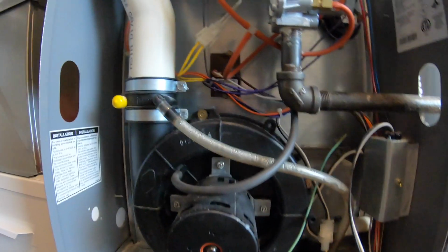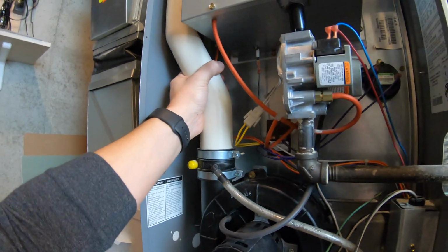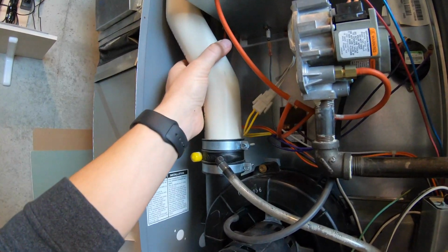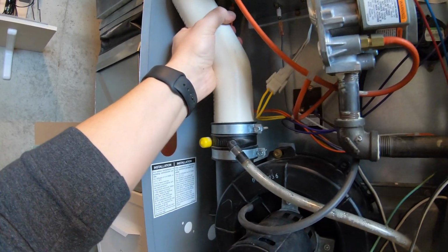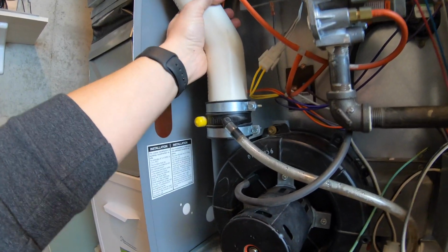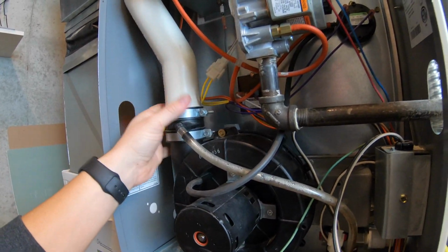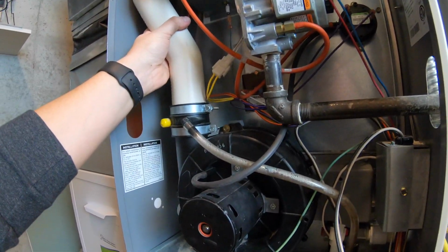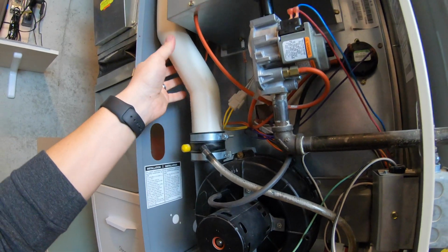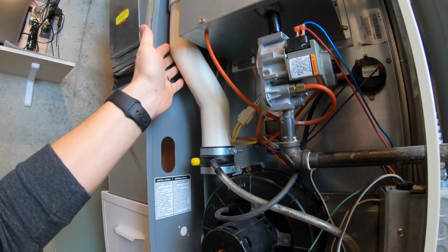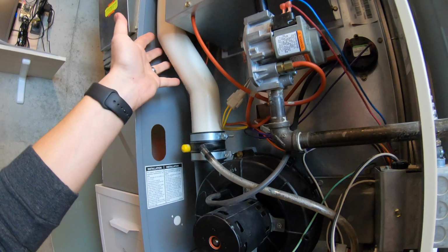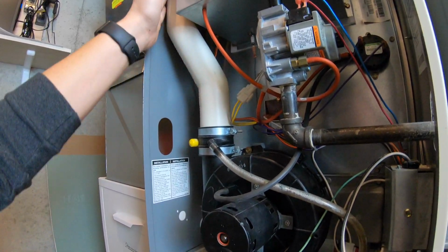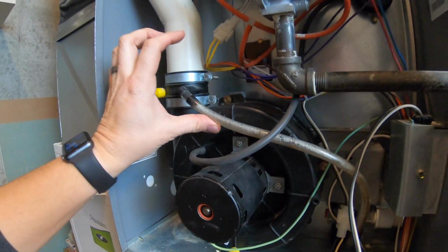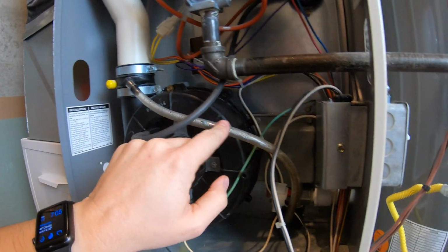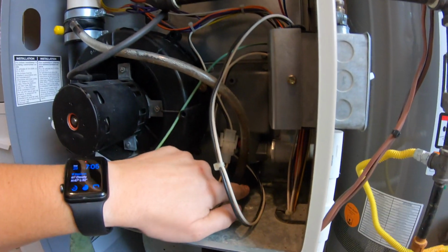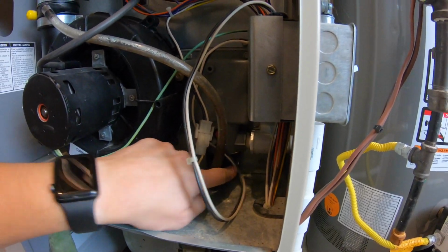Then this furnace is a condensing furnace. So the air going out through this pipe is very cool compared to your 80% furnaces or the older style furnaces that burned a lot hotter. The exhaust gas was a lot hotter coming out. So because this exhaust gas is so cool, this exhaust starts to condense inside of the piping. Water starts to roll back through this pipe. And as you can see inside of this tubing here, it's pretty wet. That spills out into this drain trap that we've got right here.